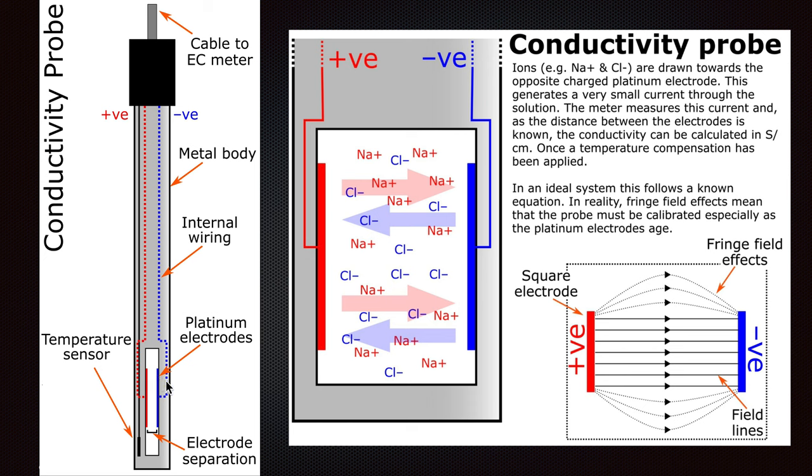Sodium and chloride ions are drawn towards the oppositely charged platinum electrodes. This generates a very small current through the solution. The meter measures this current, and as the distance between the electrodes is known, the conductivity can be calculated — once a temperature compensation has been applied. In an ideal system this follows a known equation.